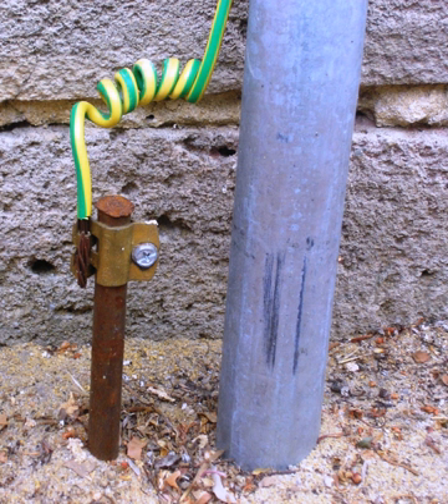Topic: Lightning protection systems. Lightning protection systems are designed to mitigate the effects of lightning through connection to extensive grounding systems that provide a large surface area connection to earth. The large area is required to dissipate the high current of a lightning strike without damaging the system conductors by excess heat. Since lightning strikes are pulses of energy with very high frequency components, grounding systems for lightning protection tend to use short straight runs of conductors to reduce the self-inductance and skin effect.